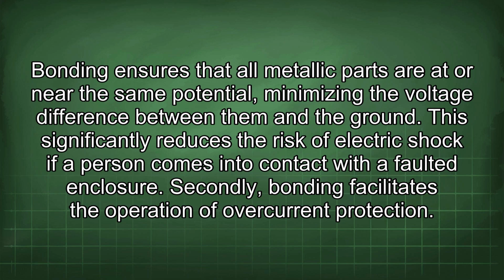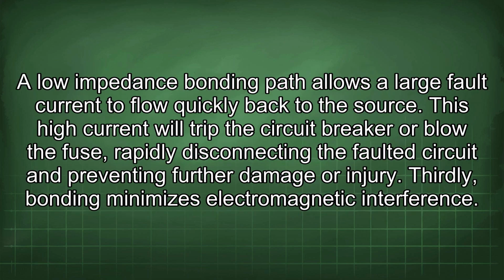Secondly, bonding facilitates the operation of overcurrent protection. A low impedance bonding path allows a large fault current to flow quickly back to the source. This high current will trip the circuit breaker or blow the fuse, rapidly disconnecting the faulted circuit and preventing further damage or injury. Thirdly, bonding minimizes electromagnetic interference.